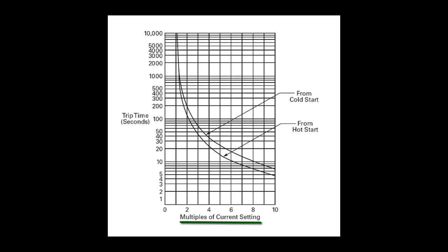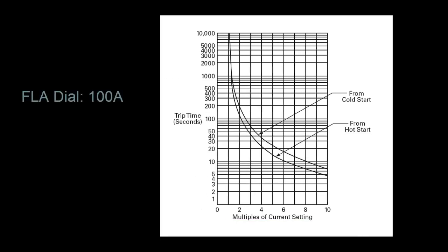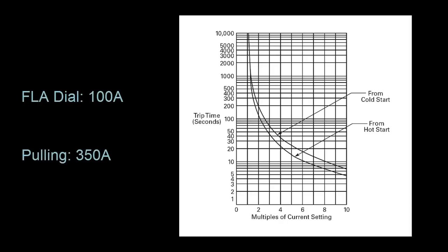We'll get to the trip class in a second. So if we have a motor that has an FLA rating of 100 amps and is constantly pulling 350 amps from a cold start, it's pulling 350% of what it should be, or 3.5 times as much. So we find 3.5, go up to the cold start curve, and it'll trip in about 50 seconds.